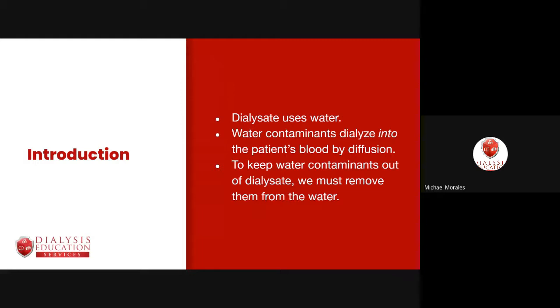The majority of the proportion of dialysate is water. With a 45X proportioning ratio, the parts of water are 42.28. The parts of acid concentrate are one, and the bicarbonate is 1.72. So again, most of dialysate is water.